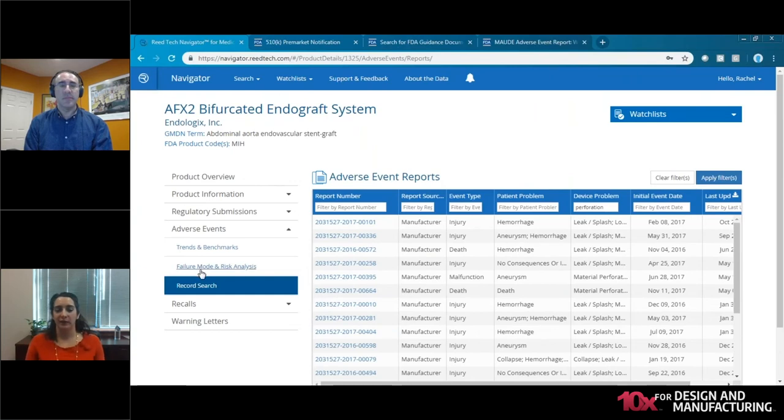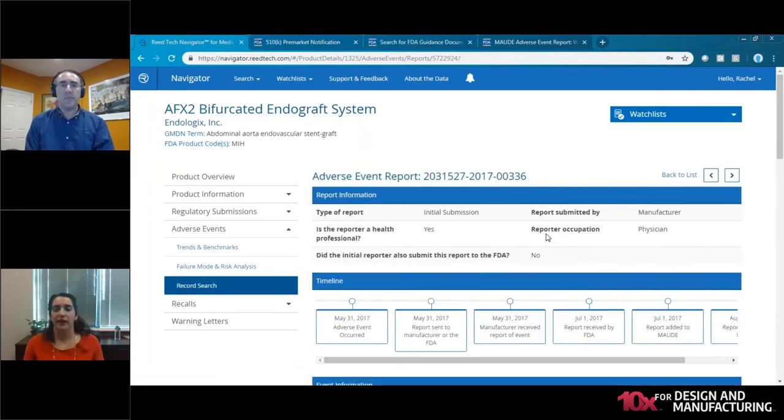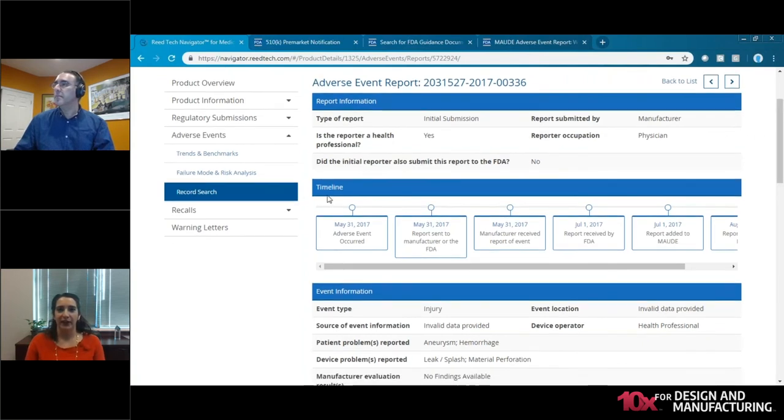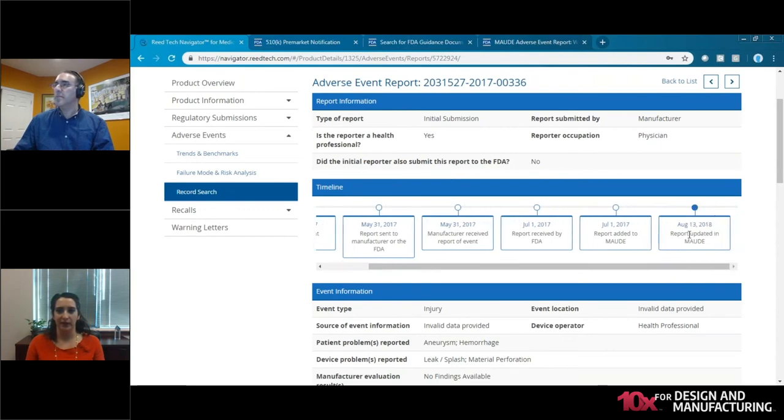Yeah, so on this, when we compare it to the industry, we can kind of see how frequently that issue is occurring. And then here I can see that full list of reports with that issue. And then I can click on one of these to get the details. This is going to have much the same information you would see in the MAUDE database, but we've organized it in a way that we think makes a little bit more sense. Tried to group information together. All the fields will always be here. They'll always be in the same place, which is something that I've noticed on the MAUDE database. It's hard for me to find the same field on multiple reports sometimes. We've also put together a timeline so you can see when the adverse event first occurred all the way to the last time that it was updated in MAUDE.